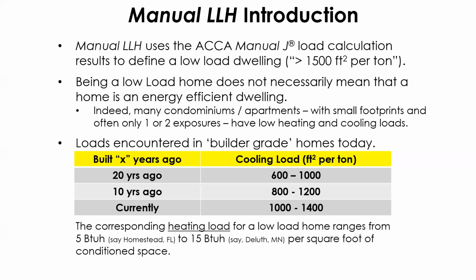So when somebody comes up with this, doing a Manual J doesn't say, well, I'm not 1500 square foot per ton, so I must have done something wrong. Being a low-load home doesn't necessarily mean it's energy efficient in today's market. Indeed, many condominiums and apartments, which I've been talking about, that have only 1 or 2 exposures have always been low-load homes and have low heating and cooling loads. But 20 years ago or so, when we did Manual J7, it could have been 600 to 1,000 square foot per ton. 10 years ago, as the homes improved, it went to 800 to 1,200 square foot per ton. And currently, we're often seeing homes in the 1,000 to 1,400 square foot per ton, and up to 2,000 square foot per ton, depending on what the people decided to do with their home that's above and beyond the requirements in the code.